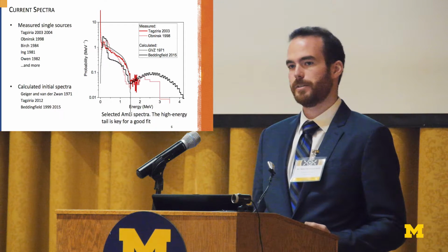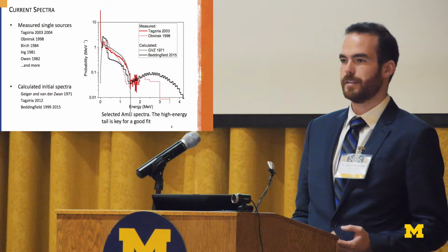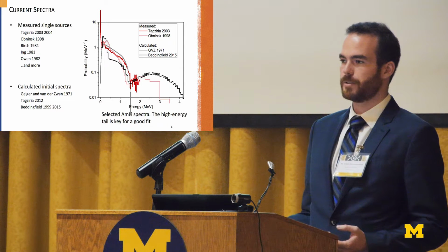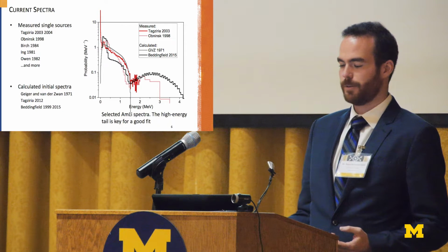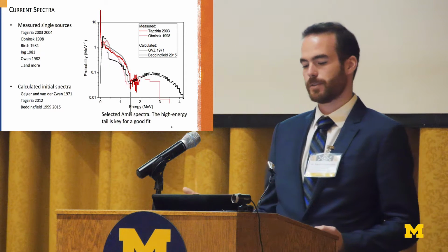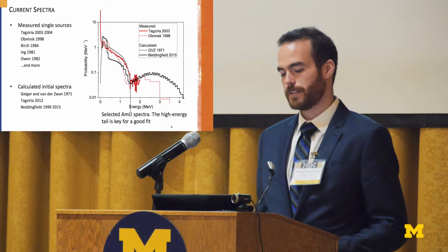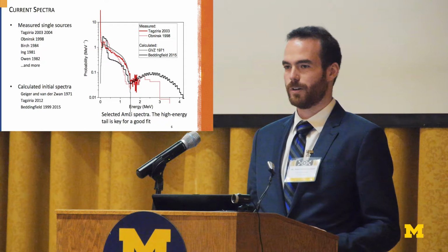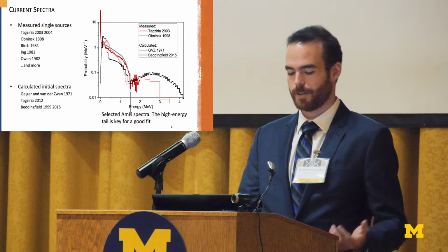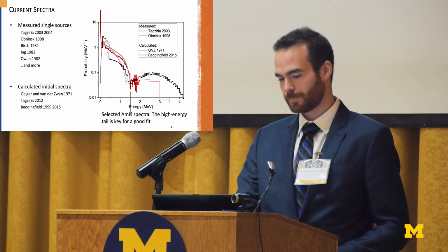And so the reason the high energy part is important is because in detectors like the UNCL, they assume that there's no uranium-238 fission. But the U-238 fission cross-section really increases quite a bit in those higher energies. And so depending on what your spectra is, that assumption can be more or less true, and it probably also, again, varies from source to source.